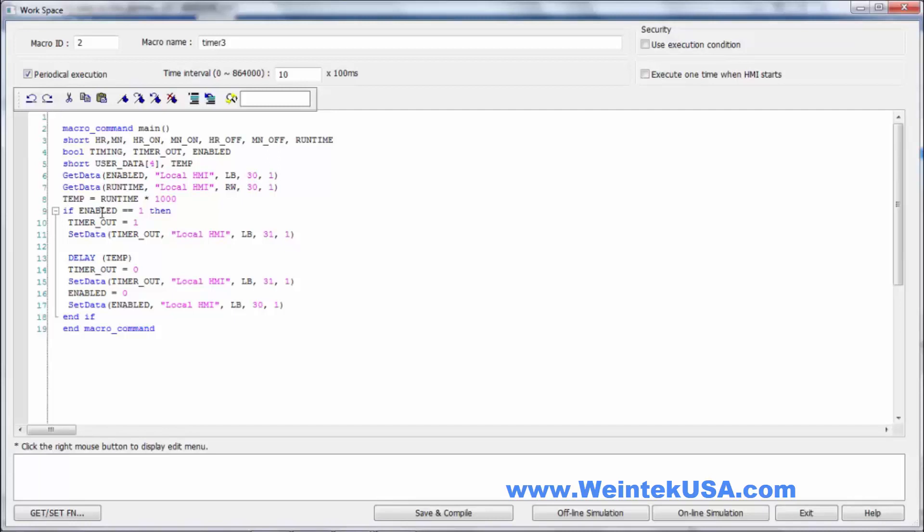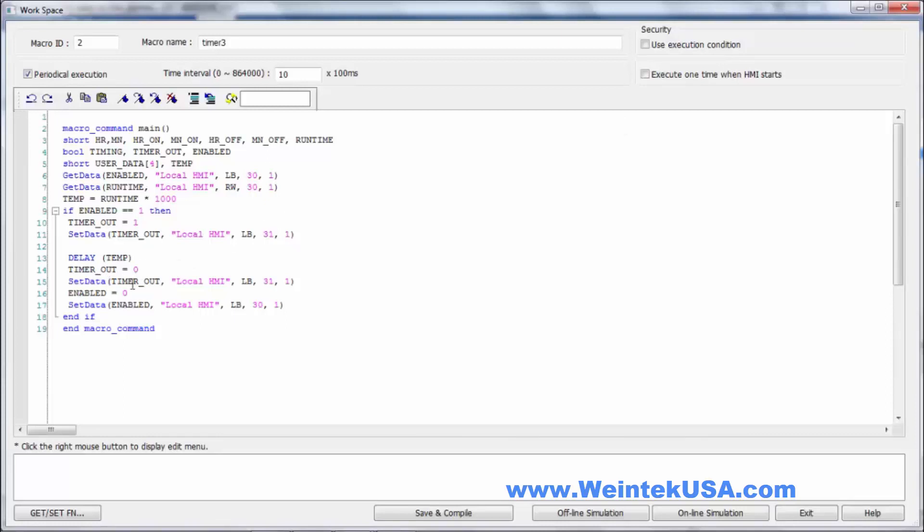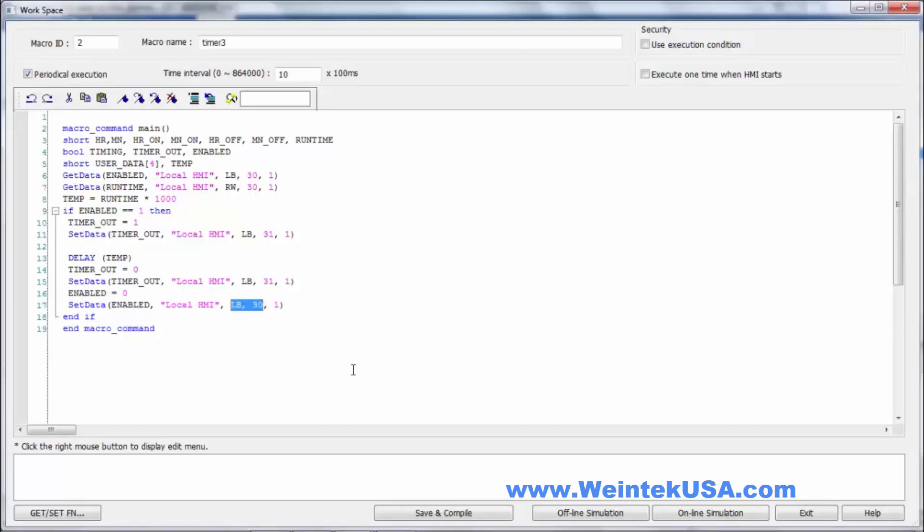If enabled equals one, then we set timer out to one. Write that to our output bit. Here we're putting the value of run time times a thousand into temp. We do a delay for our temp value. Once that delay is up, we write a zero in the timer out and write that value to our output bit LB31. We write a zero to our enable object and write that value to our enable bit LB30.